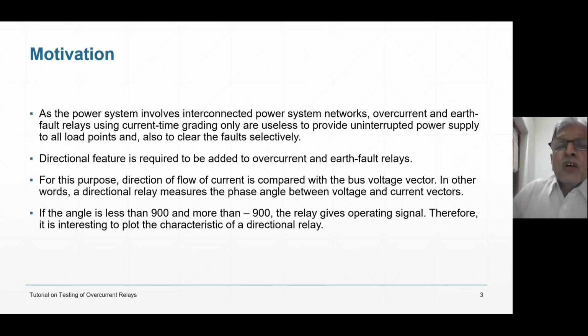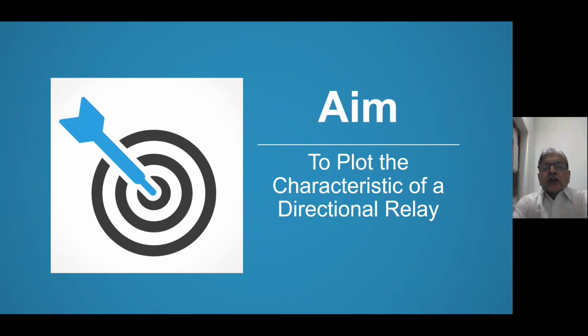If the angle is more than that, considering 4 quadrants, if I take I as a reference vector and V lies in any of the 4 quadrants - if V lies in first or fourth quadrant, the relay will operate. If it lies in second or third quadrant, the relay will not operate, even though the current is more than plug setting, even though it's fault current. That is the requirement of a directional relay. Our aim is to plot the characteristic of that directional relay.